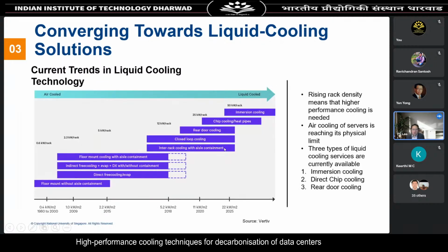If you look at the comparison of different cooling techniques as a function of rack density, what's clear is when your rack density starts to exceed, for example, 12 kilowatts per rack, we have to look at more effective and higher performance cooling solutions. So in particular, I'd like to point your attention to three techniques.